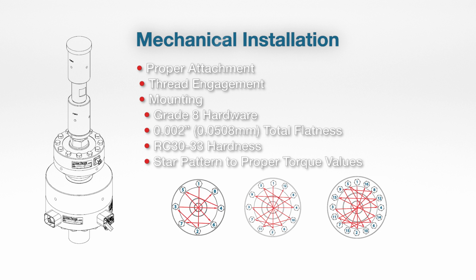And what we're doing there is we're ensuring that we won't have any repeatability issues due to thread engagement changing through the center of that flexure. So if you can't provide a preload on the load cell, then we do have some torque values available in our installation guide that will do a pretty good job of getting the threads loaded up in a similar fashion. But again, the whole point with the preload is that we've got the threads engaged to a point that is higher than the load cell should see during use. And by doing that, it's just going to help with repeatability and for best performance.